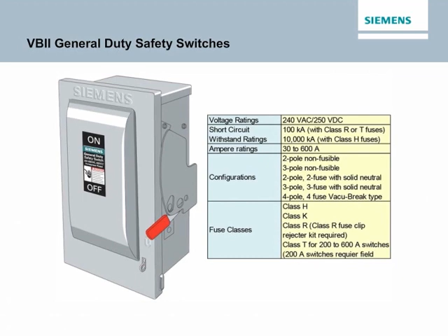The following configurations are available: 2-pole or 3-pole non-fusible, 2-pole, 2-fuse and solid neutral, 3-pole, 3-fuse and solid neutral, 4-pole, 4-fuse Vacu-Break type. Fusible switches will accept the following UL class fuses: Class H, Class K, Class R. A Class R fuse clip rejector kit is available and required. Class T is available for 200 to 600 amp switches, and 200 amp switches require a field adapter kit.